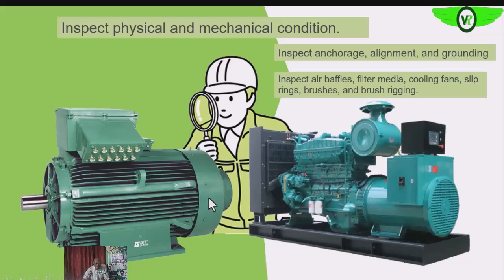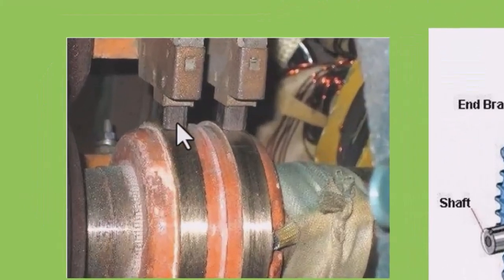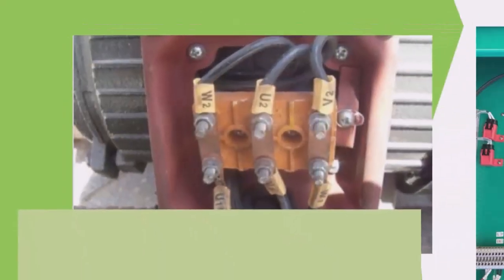Then if the alternator or the motor has brushes, you have to check to see that the proper tension is maintained between the brush and the slip ring. So those are some of the things that I want to be very sure of, because if the spring pressure on the brush is not enough, that can result in partial contact that may eventually result in arcing, and continuous arcing can result in the damage of that slip ring and the entire unit.